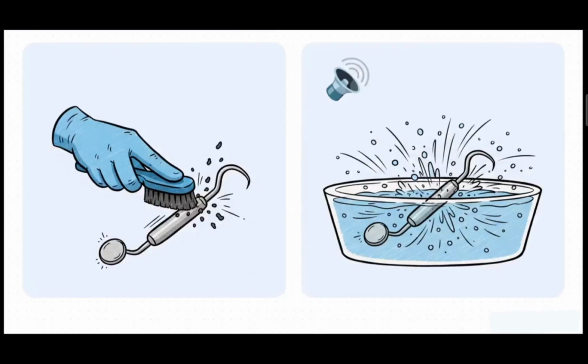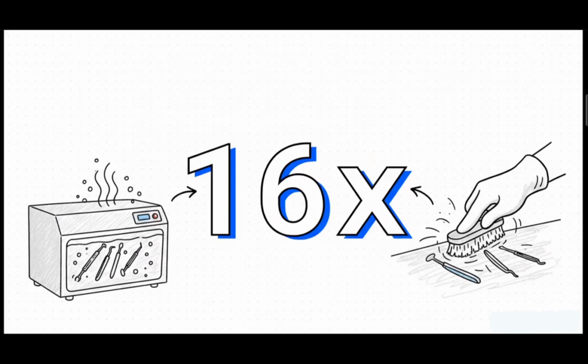So how do they get to this level of clean? Well, there are two main ways. First, you've got manual cleaning, which is just what it sounds like: someone scrubbing each tool by hand. But really, the modern gold standard is ultrasonic cleaning. This thing uses high-frequency sound waves to create millions of tiny little bubbles that literally blast the debris right off the instrument's surface. And the difference between these two methods, it's not small. It is staggering. Get this: ultrasonic cleaning is 16 times more effective than doing it by hand. I mean, that's just a massive leap forward in safety and efficiency. It really shows you how important technology is in keeping us safe at the dentist.